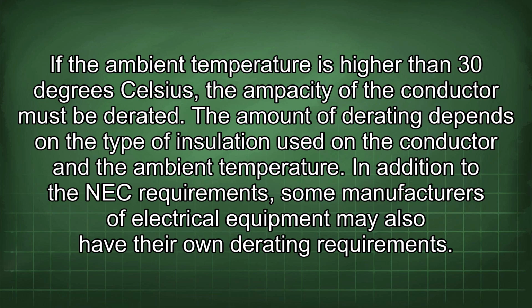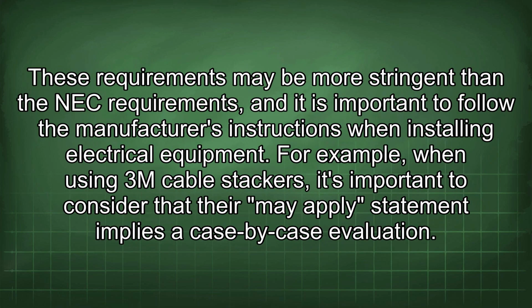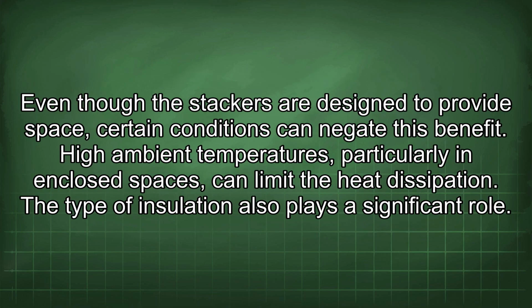In addition to the NEC requirements, some manufacturers of electrical equipment may also have their own derating requirements. These requirements may be more stringent than the NEC requirements, and it is important to follow the manufacturer's instructions when installing electrical equipment. For example, when using 3M cable stackers, it's important to consider that the "may apply" statement implies a case-by-case evaluation. Even though the stackers are designed to provide space, certain conditions can negate this benefit.